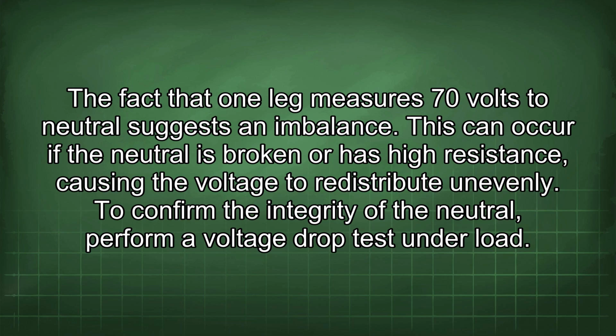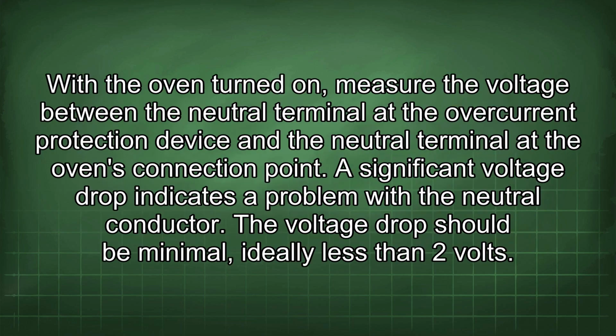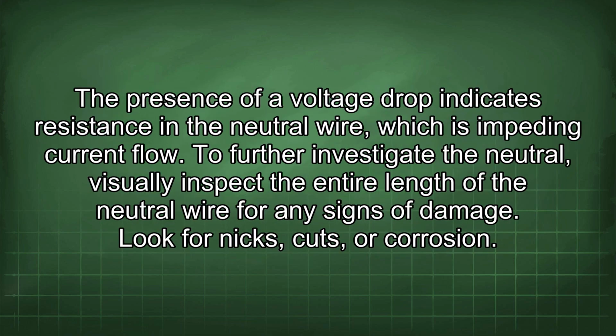To confirm the integrity of the neutral, perform a voltage drop test under load. With the oven turned on, measure the voltage between the neutral terminal at the overcurrent protection device and the neutral terminal at the oven's connection point. A significant voltage drop indicates a problem with the neutral conductor. The voltage drop should be minimal, ideally less than 2 volts. The presence of a voltage drop indicates resistance in the neutral wire, which is impeding current flow.